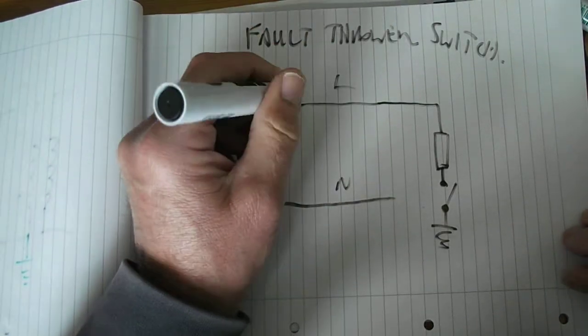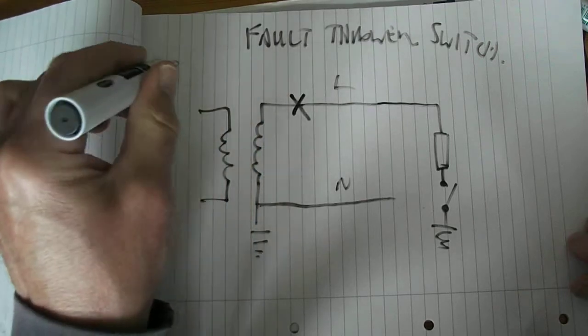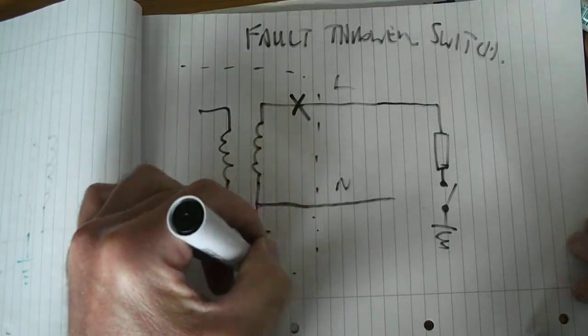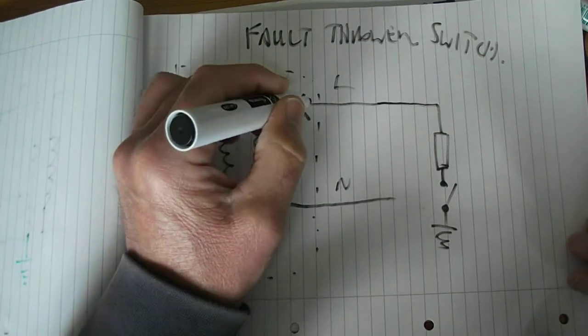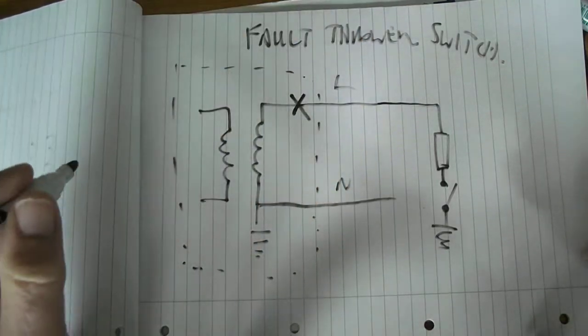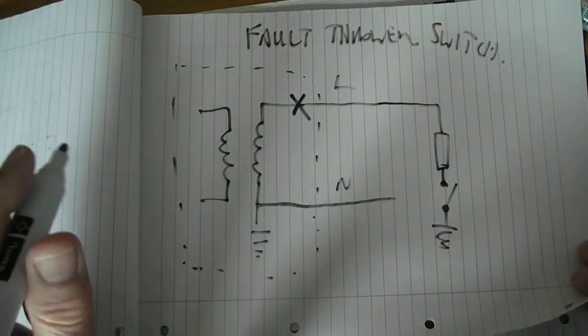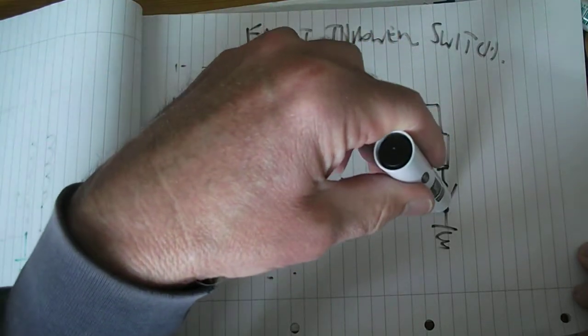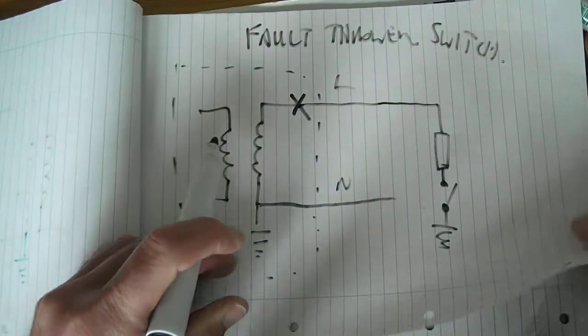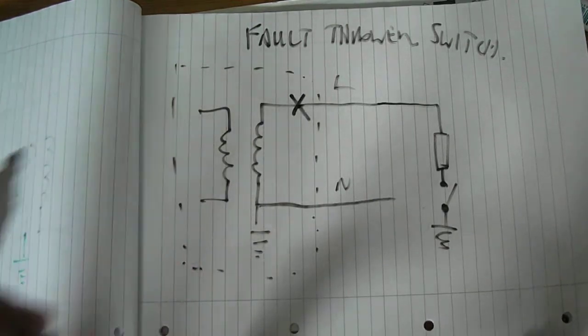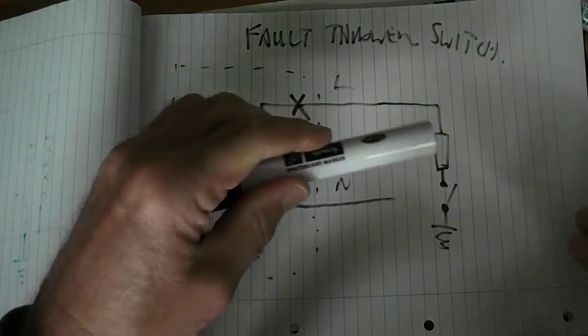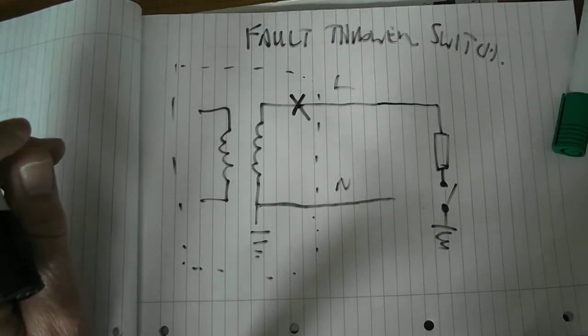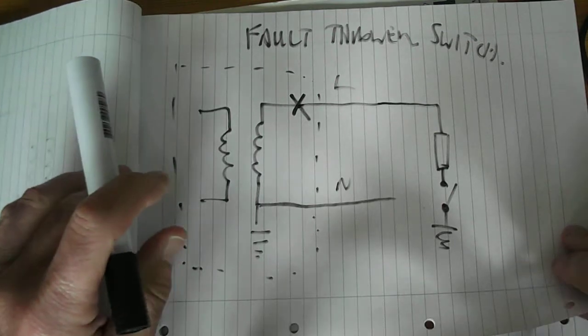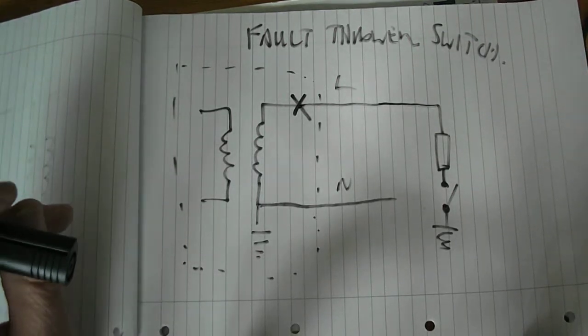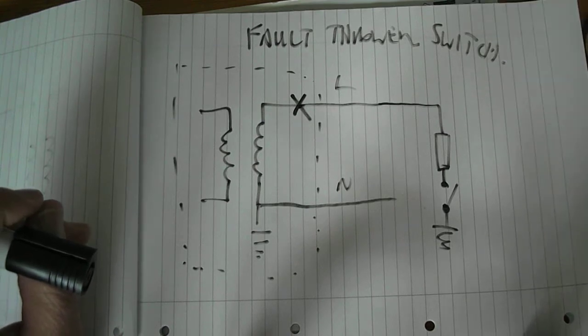And it's normally to test a circuit breaker, which is usually in the substation. So the fault thrower switch will test the circuit breaker from a distance away from the substation. So that's what a fault thrower switch is for. So there's our circuit breaker inside the substation, and there's our fault thrower switch remote from the substation. Okay. It acts a little bit like the button on an RCD in your consumer unit. The test button does a similar sort of thing, really. Okay.